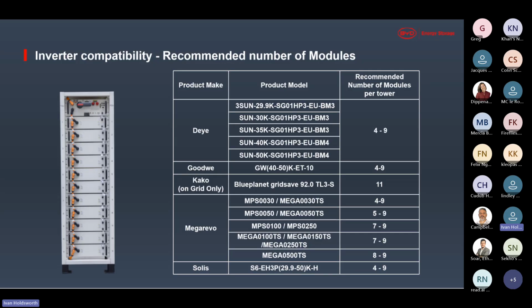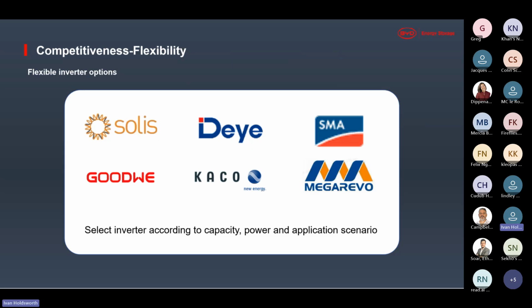It's also very important to have the same number of modules in each tower if you've got towers in parallel. So for example, if you've got 2 or 3 towers in parallel, those towers always have to have the same number of modules in that tower, because the voltage of that tower depends on the number of modules in the tower. If you're putting them in parallel, they have to have the same voltage. And here we can see a brief summary of the compatible inverters.